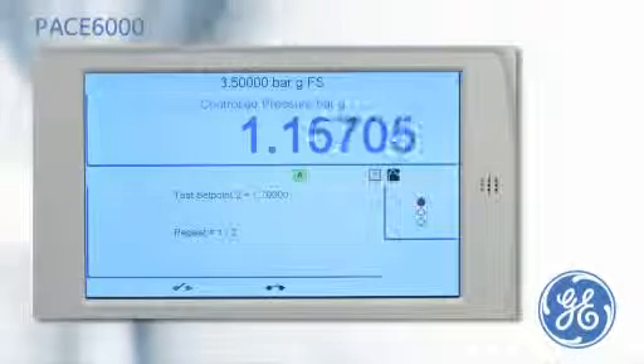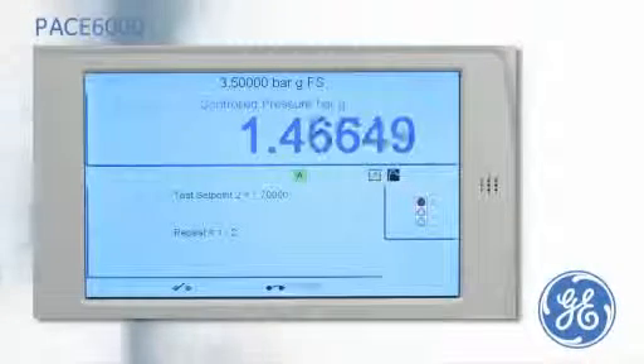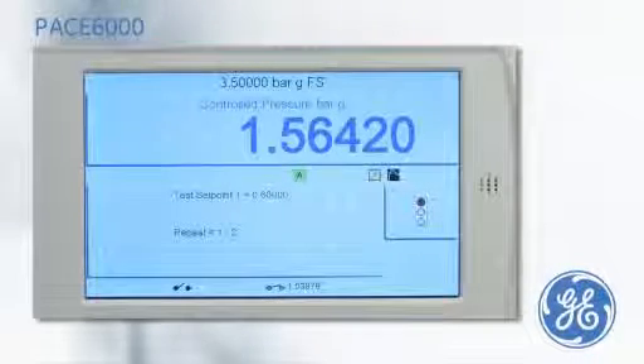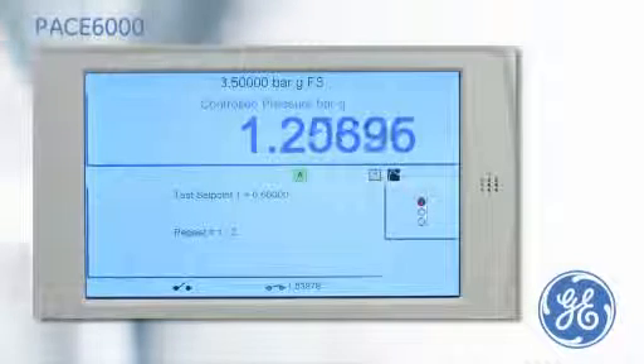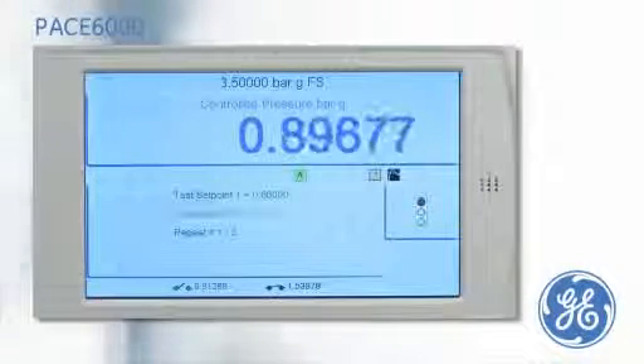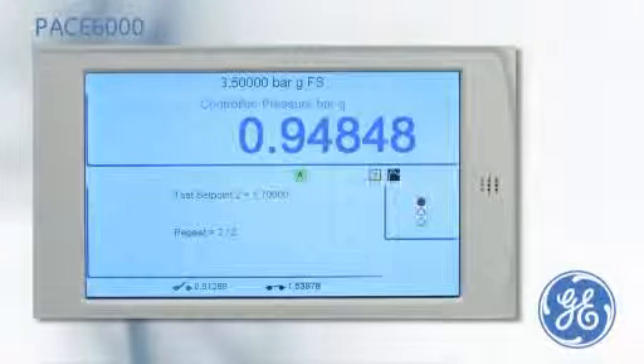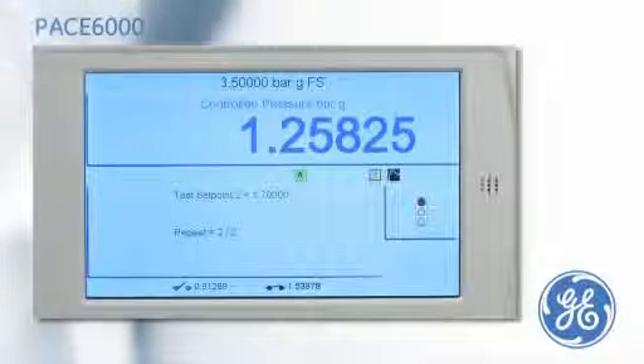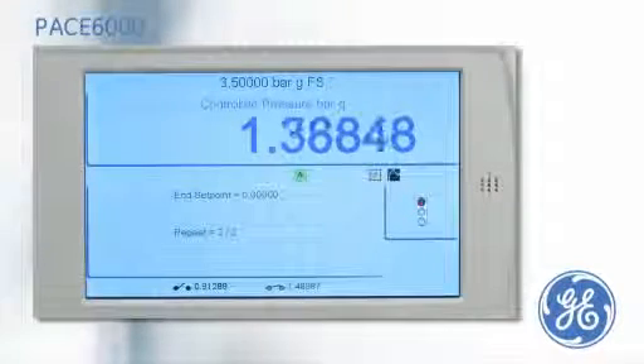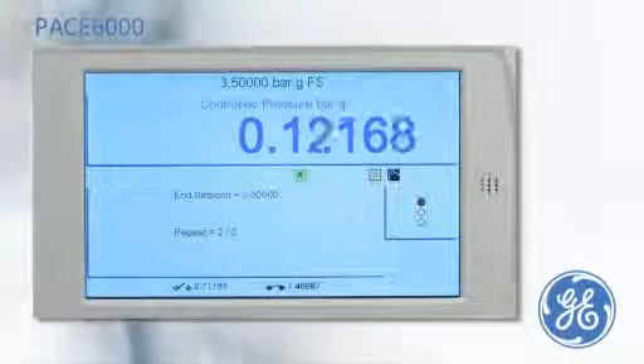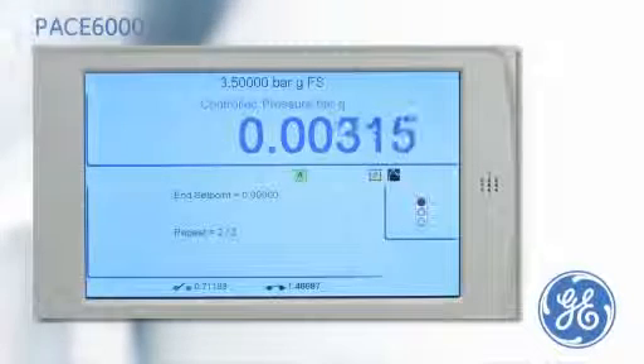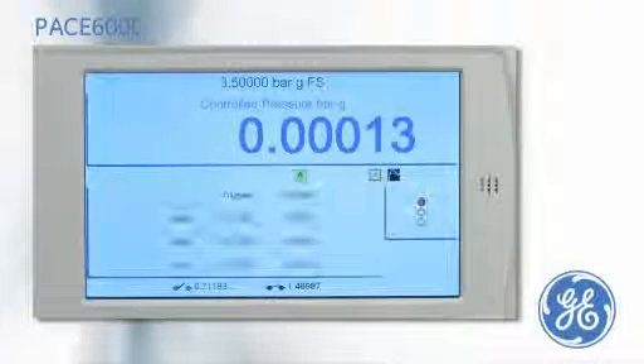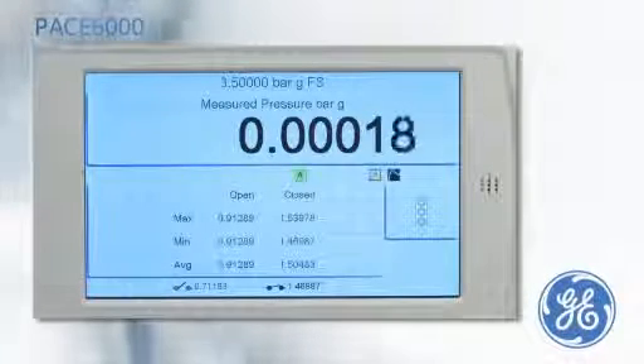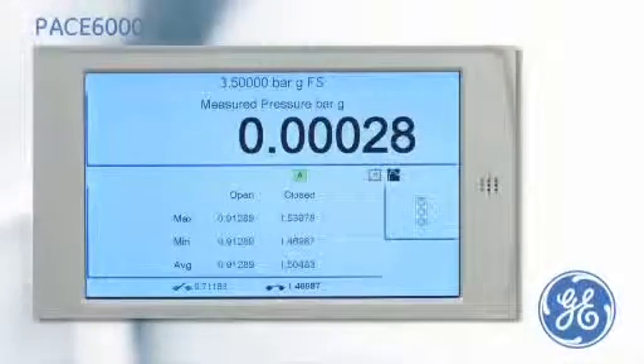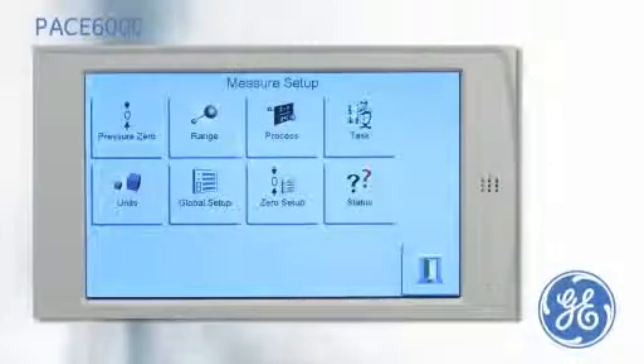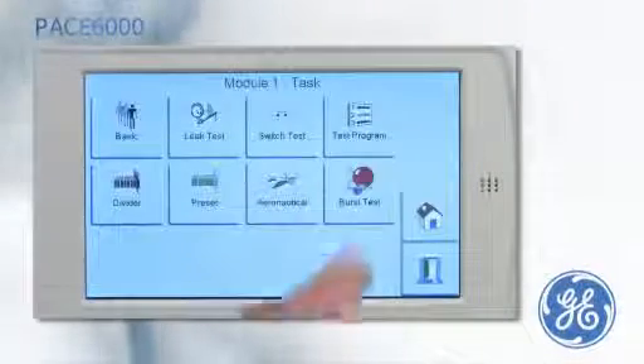The pressure is slowly increased until the contacts change at 1.5 as indicated at the bottom of the screen. The pressure is then reduced until the contact change is captured at 0.81. The test is now repeated with the contact change points being captured. The maximum, minimum and average switching points of both tests are calculated and displayed. For any customers who have an automated test, we have a dedicated test program task.